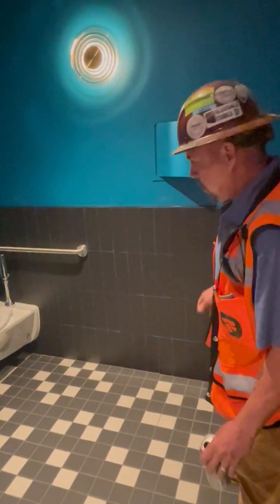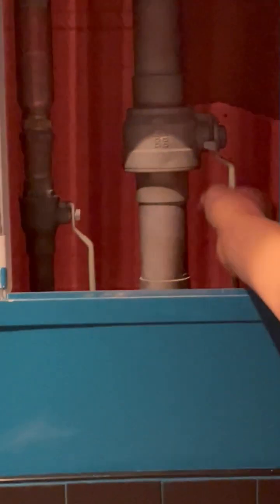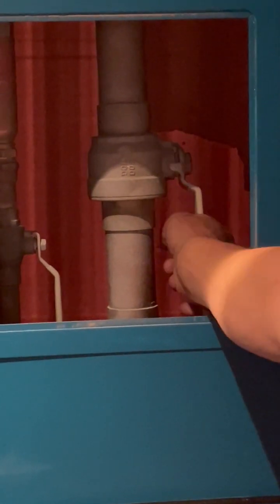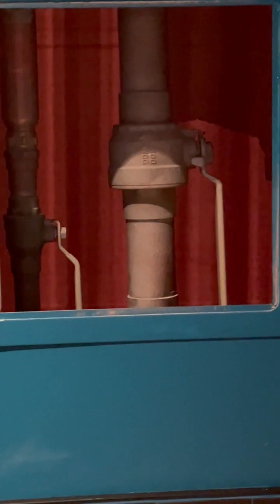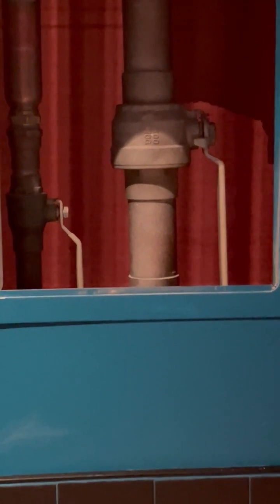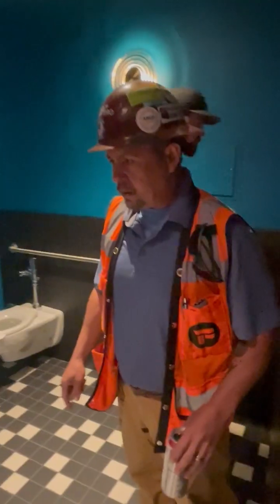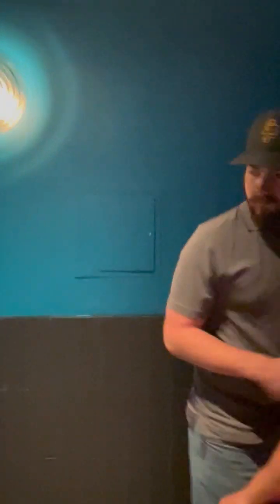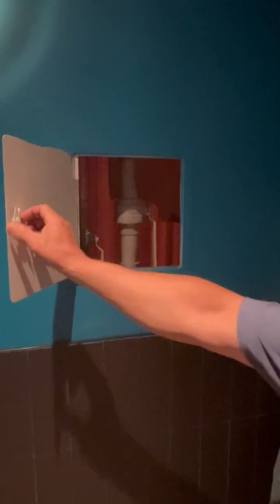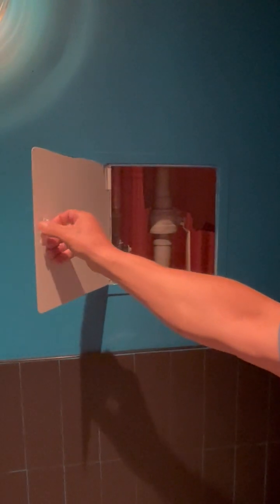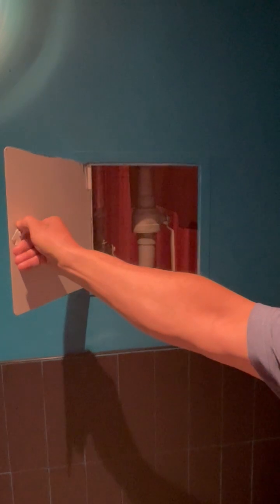Okay. Same thing. There's a 12 by 12 access panel. This shut off valve here, just pull this up. This will shut down and isolate the entire men's and women's restroom on the lower level, including lavatories. Cool. And in order to open this, what do you need? In order to open this, we need a flathead screwdriver. Just turn it counterclockwise and pull it right open. Great. And there's a little lever here that'll lock it. Once you close it, turn it counterclockwise and it'll close right up.